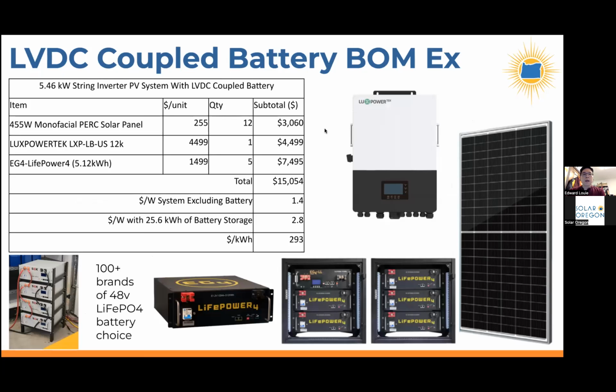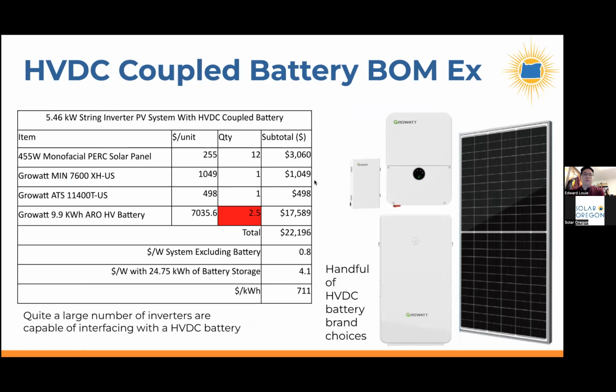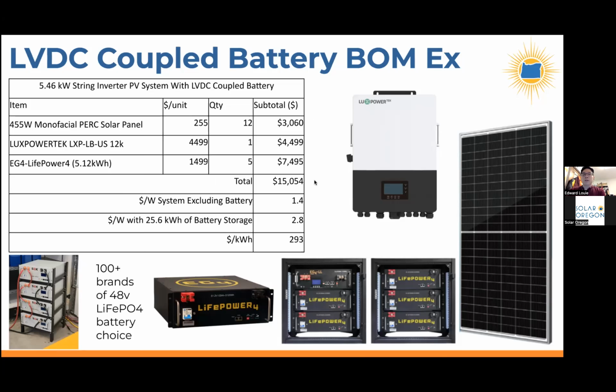Okay, so now looking at a system with low voltage DC coupled batteries. One of the things we can see in this example is that the inverter costs a lot more than other inverters. This inverter is $4,500 versus even an inverter that's compatible with high voltage DC battery, which is only $1,050. So they cost a lot more, but where is the savings then?